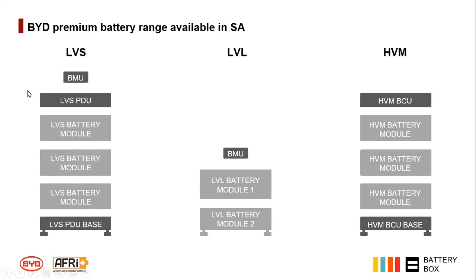All of your wire connections to your inverter happen on the PDU for power, and you do require an external BMU per battery bank — the BMU is the interface between your inverter and your batteries. The HVM is a very similar design, with a tower consisting of the BCU base, modules, and BCU top. You can have between 3 and 8 modules on the HVM, and the only difference in topology is that you don't need a BMU between your battery and your inverter.